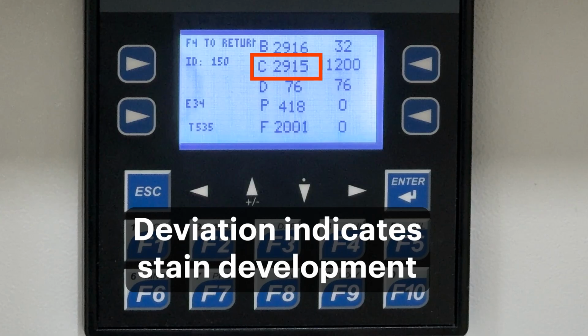A large deviation in a short period of time indicates rapid stain development and typically results in high concentrations displayed. If the C value is nearly equal to the B value, no stains are forming on the tape.